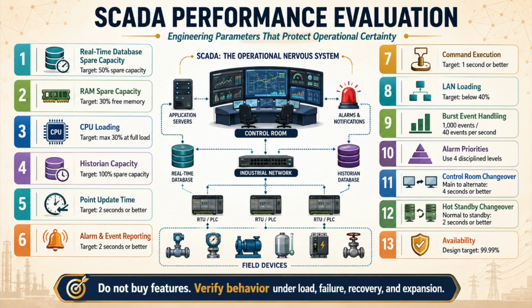Point update time depends on field scan time, protocol efficiency, network latency, server load, display subscription, client rendering, database optimization, and communication driver configuration. So engineers must separate field scan time, server database update time, display refresh time, and total operator visible update time. Critical process values may need faster scan classes, while slow diagnostics do not, and forcing every point into the fastest scan class only overloads communication without operational value.